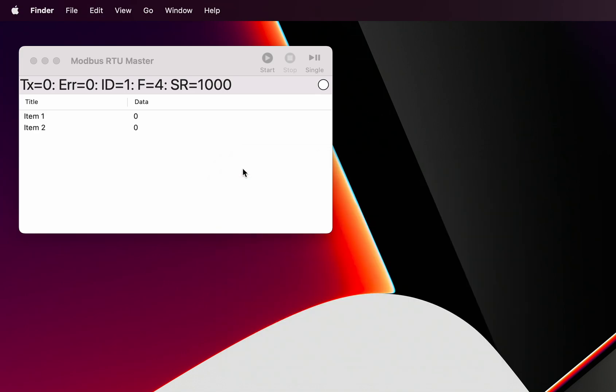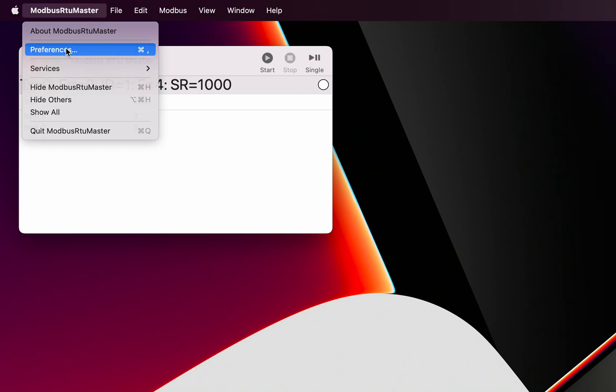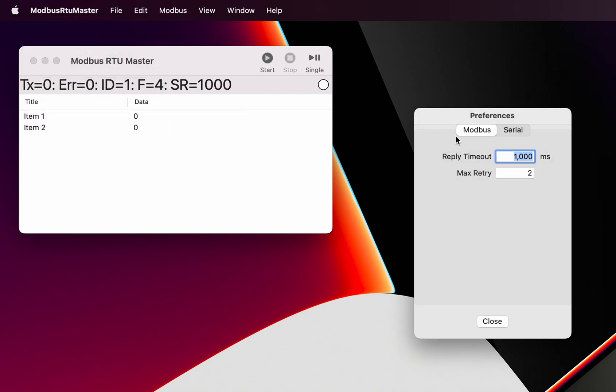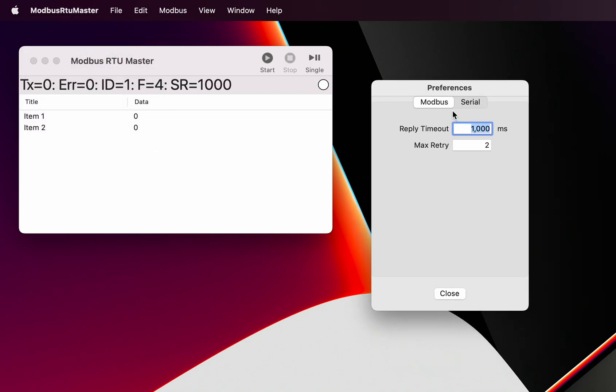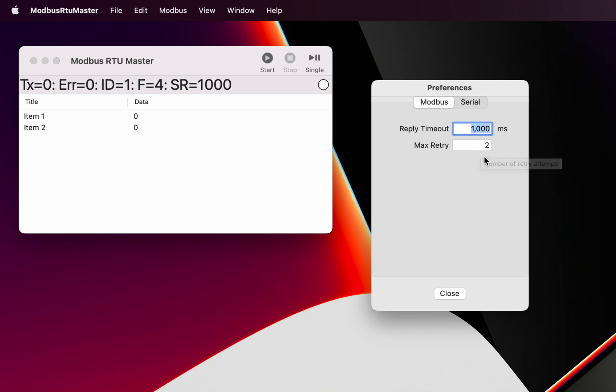Let's have a look at the preferences section of Modbus RTU Master. We can configure our Modbus timeout - this is a reply timeout when the master requests information from the slave. It will time out if it hasn't received a reply after the time stated in here, but it will do some retries. At the moment we've got that set to a maximum number of two retries, so it'll try once and if it gets no reply it'll try another two times before it says that connection is not working.